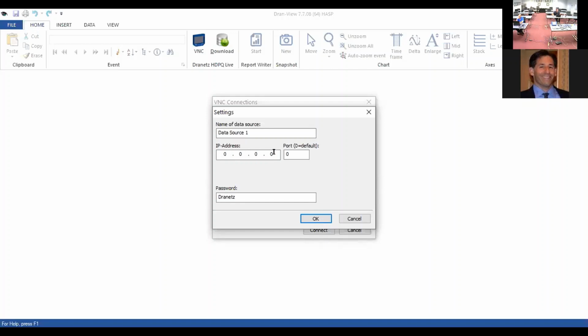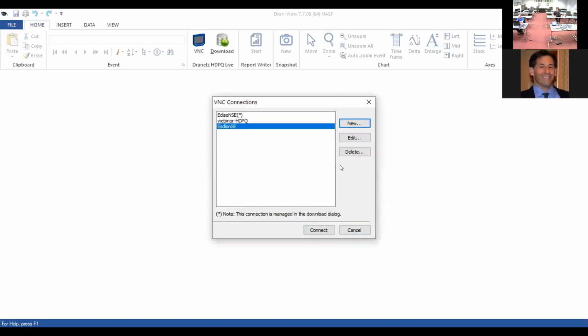Now the instrument can basically acquire IP addresses in 1 of 2 methods: static, which we recommend, or dynamic, which is DHCP. So if the instrument is on a local area network, you can have it get its IP address from a DHCP server, but our recommendation in remote setups is usually to have a static IP address assigned to the instrument. So in this case, you would enter the appropriate IP address, and once you've done that, you're ready to connect to it.